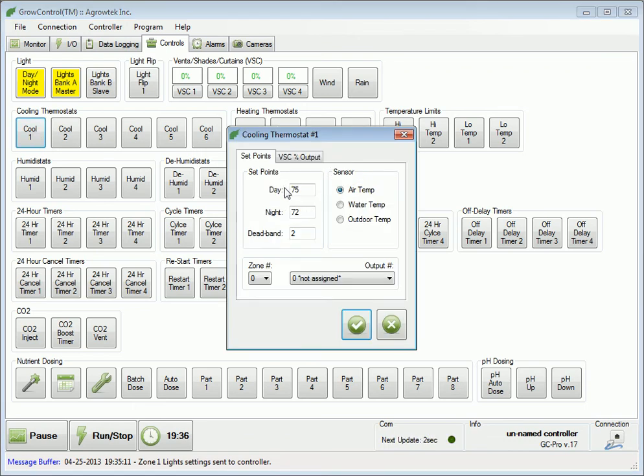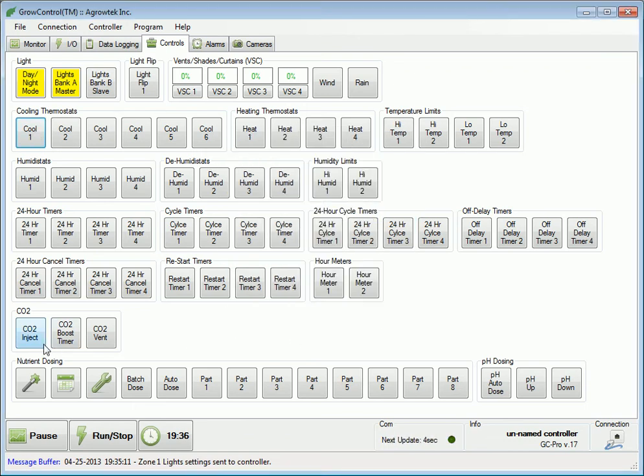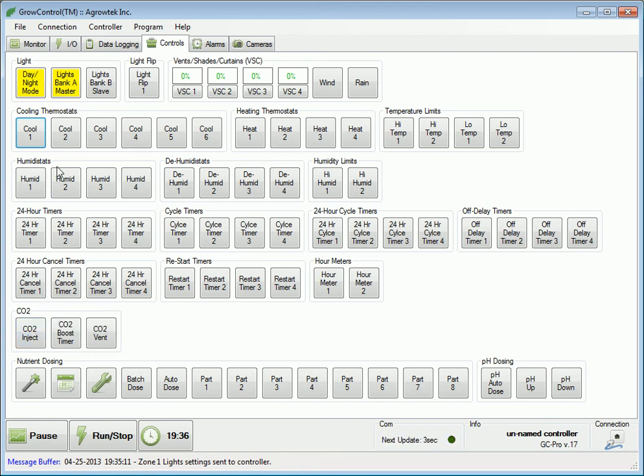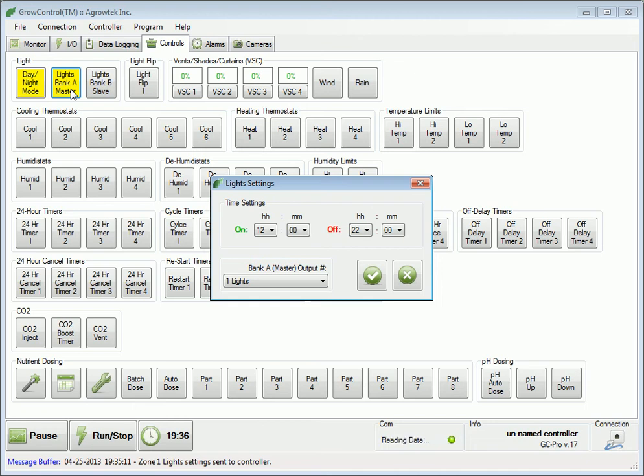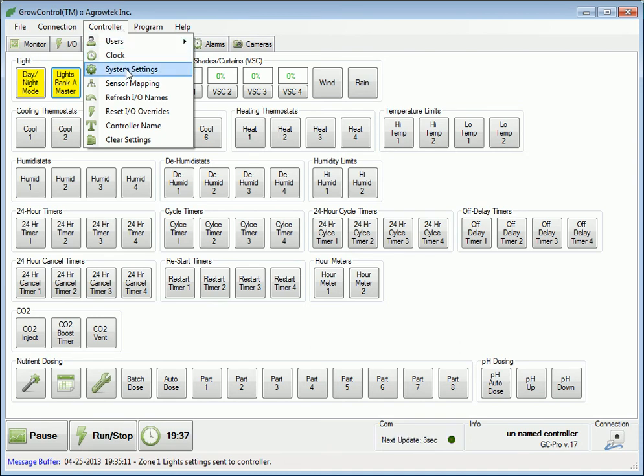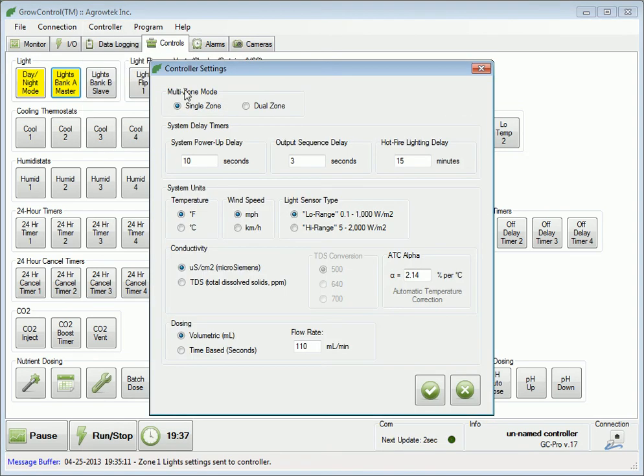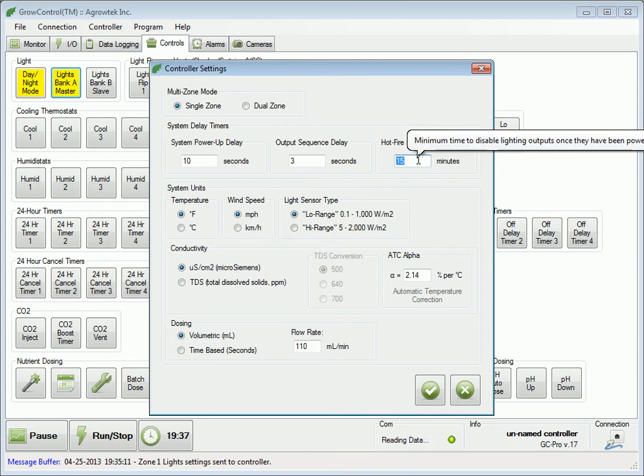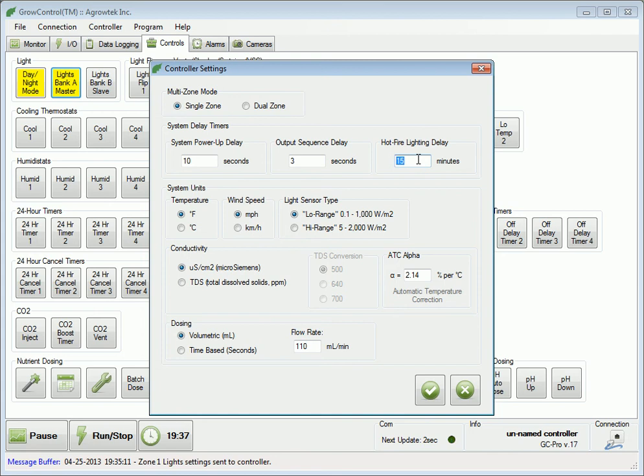When in day mode, the controller will use all of the functions that are in the day set points. Additionally, functions that are only allowed to operate during the day, such as CO2, will be allowed to operate. When the off time is reached, the lights will be turned off and the controller will enter night mode. Additionally, lighting outputs are protected by a short cycle delay timer. This hot fire delay, or short cycle time, prevents the lighting outputs from accidentally being turned on for a minimum set amount of time after they have been turned off. This is necessary with HID lights to prevent hot firing and potentially damaging the bulbs or ballasts.